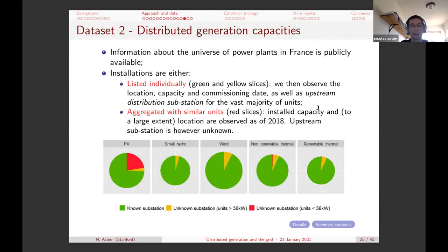Now we have to combine that with distributed generation. We have to be able to say this load duration curve or this ramp duration curve has been observed when there was that amount of distributed generation connected to this substation. The good thing is the universe of power plants in France is publicly available since 2017. So we actually observe each power plant. And for most of them, we observe them at the individual level. So it's one observation, one plant. And the dataset reports which distribution substation this distributed generation unit connects to. So for all the green part here of these pie charts, we actually observe perfectly to which substation a given distributed generation unit connects.